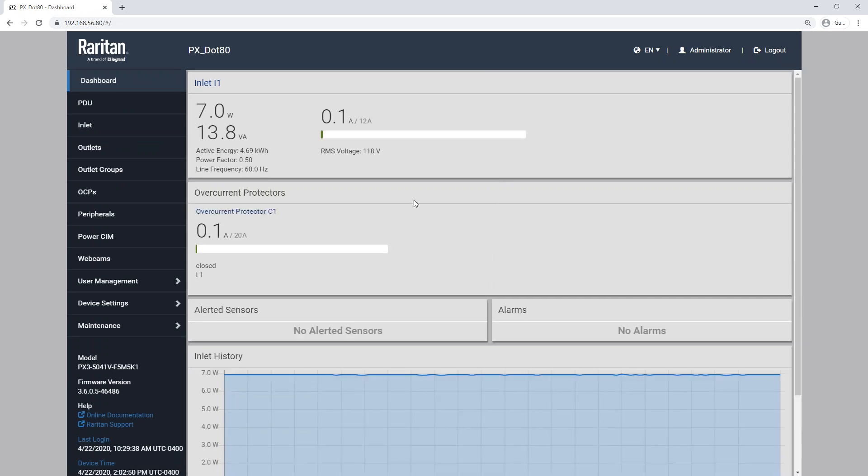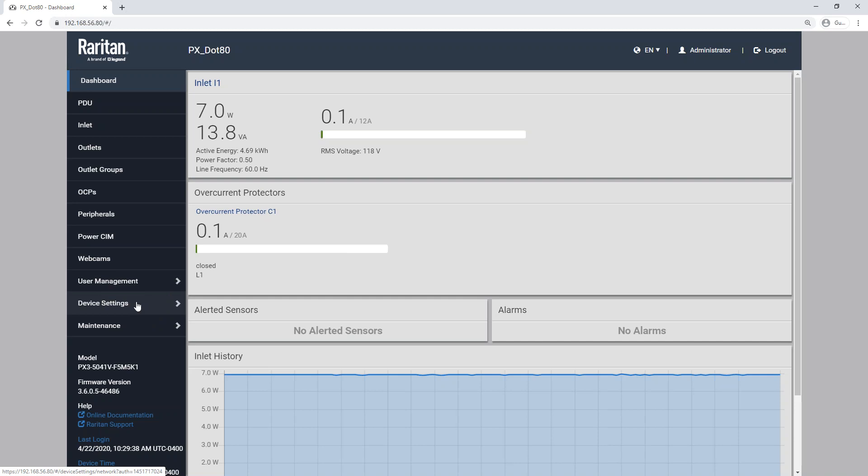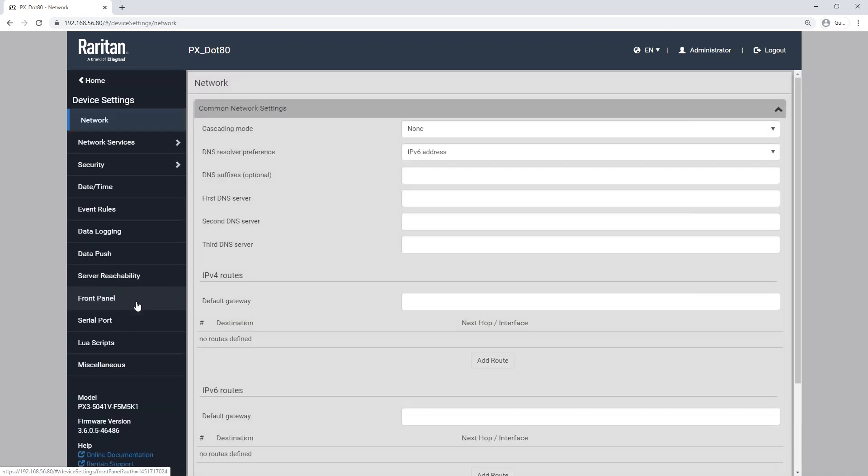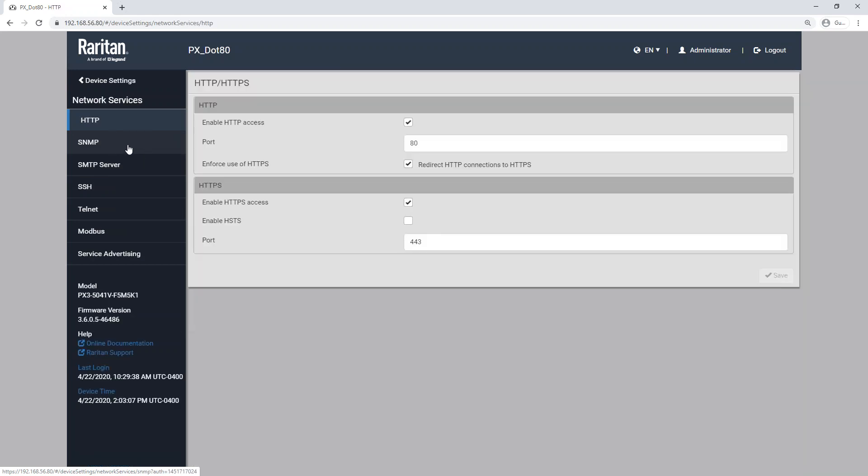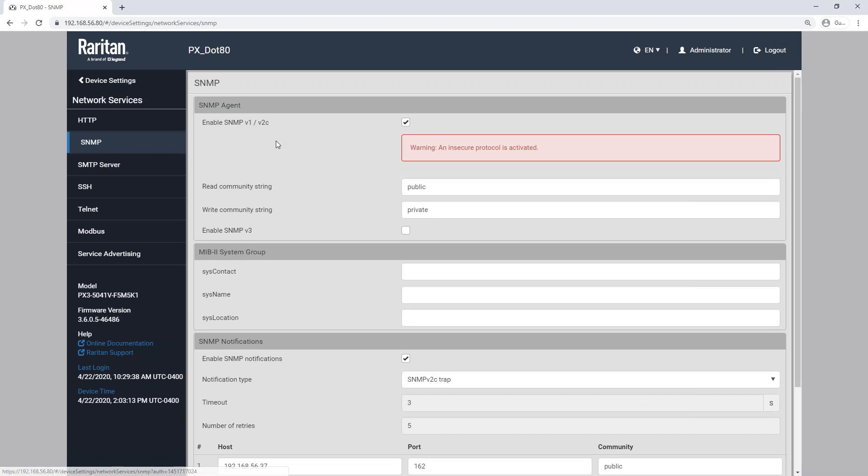So now we can see our dashboard here. On the left hand side of the menu down towards the bottom, you'll see device settings. So we're going to click on that menu option. And then back up near the top, we have a sub menu called network services. And then the second option down is going to be SNMP. So we have our SNMP agent set up here with SNMP V1 and V2C enabled, and we've got our read and write community strings plugged in there. Now this is different than setting up SNMP notifications.